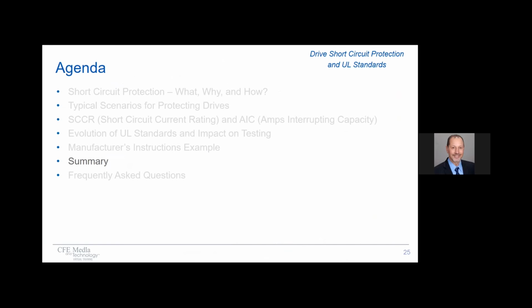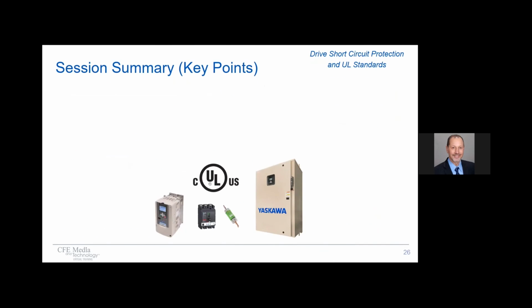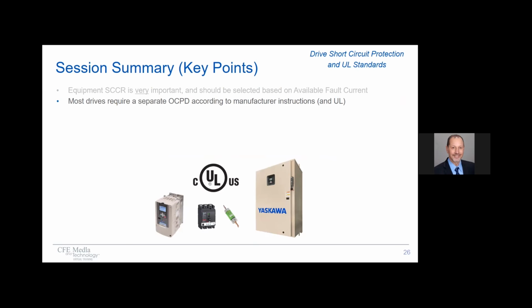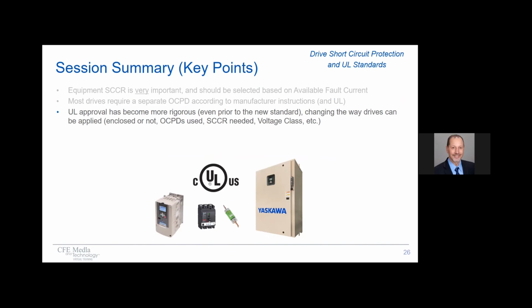Now that actually completes all of our related topics for today, but I want to leave you with the following key takeaways. In summary, equipment withstand or short circuit current rating is very important and should be selected based on available fault current. Most drives require a separate protective device according to manufacturer instructions and of course UL. And UL approval has become much more rigorous even prior to the new standard, changing the way drives can be applied, such as whether it's enclosed or not, protective device used, the withstand rating needed, the voltage class, etc.